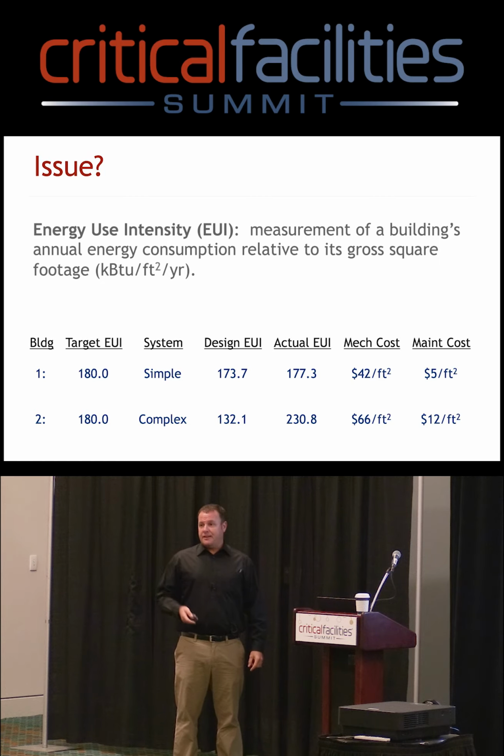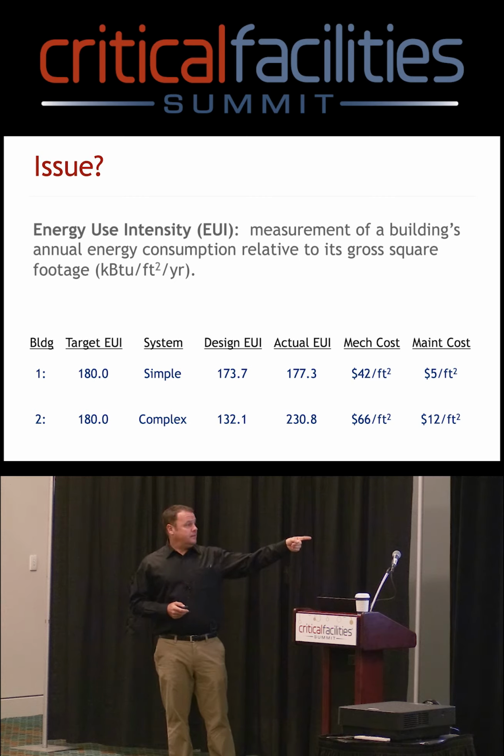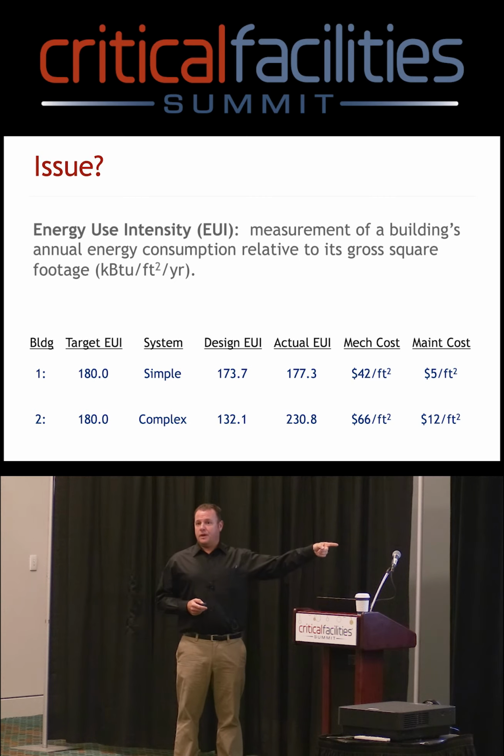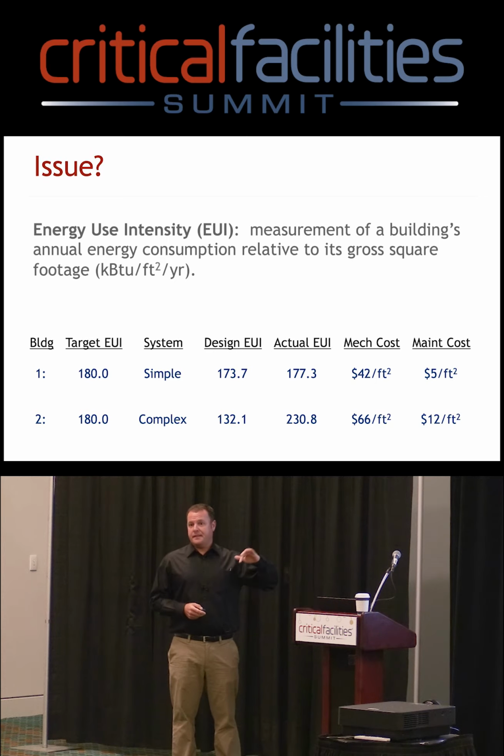The problem is a year later, the EUI for the simple, we're at a solid 177. We're continuing to meet the project requirements. The complex building, we're at 230. Okay, this is indicative of a system that's too complicated to be maintained.